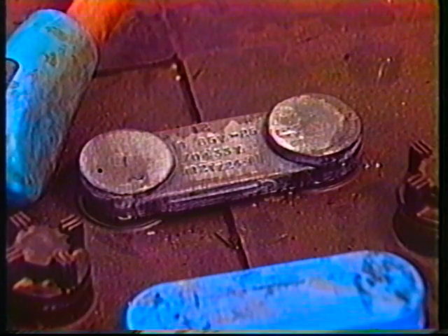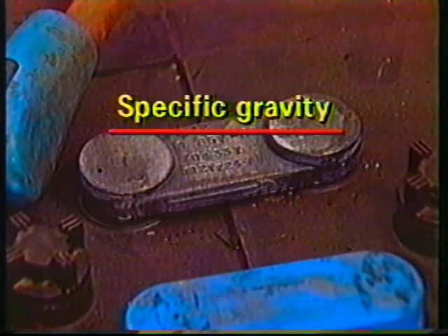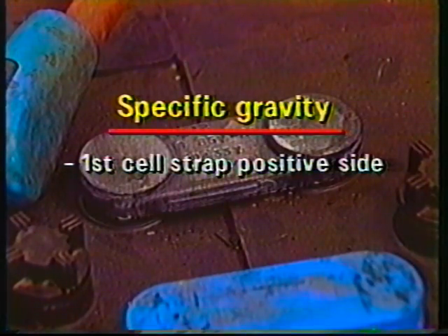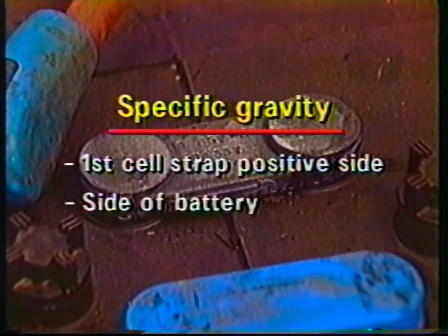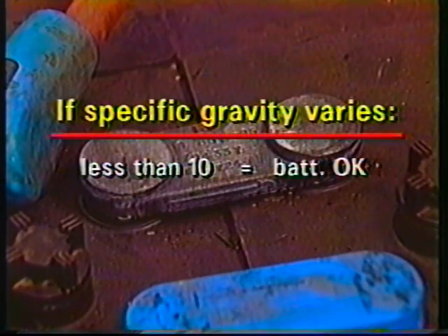Compare the true reading you get to the specific gravity number listed on the battery's nameplate. It's located either on the first cell strap of the positive battery post or on the side of the battery. If this information cannot be found on the battery, contact the battery distributor. If the reading varies less than 10 points, the battery is in good condition.